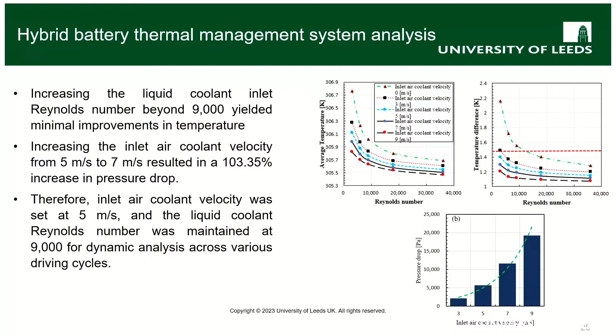So these are some of the results. We looked at different inlet velocities for air and different flow rates, which translate to Reynolds number. We realized that increasing the liquid coolant inlet Reynolds number beyond 9,000, as you can see for most of the graph, it becomes kind of flat. So there's no point to increase the velocity and flow rate further, as it doesn't give us much benefit for the plate cooling. We concluded that we can keep 9,000 as a criteria.